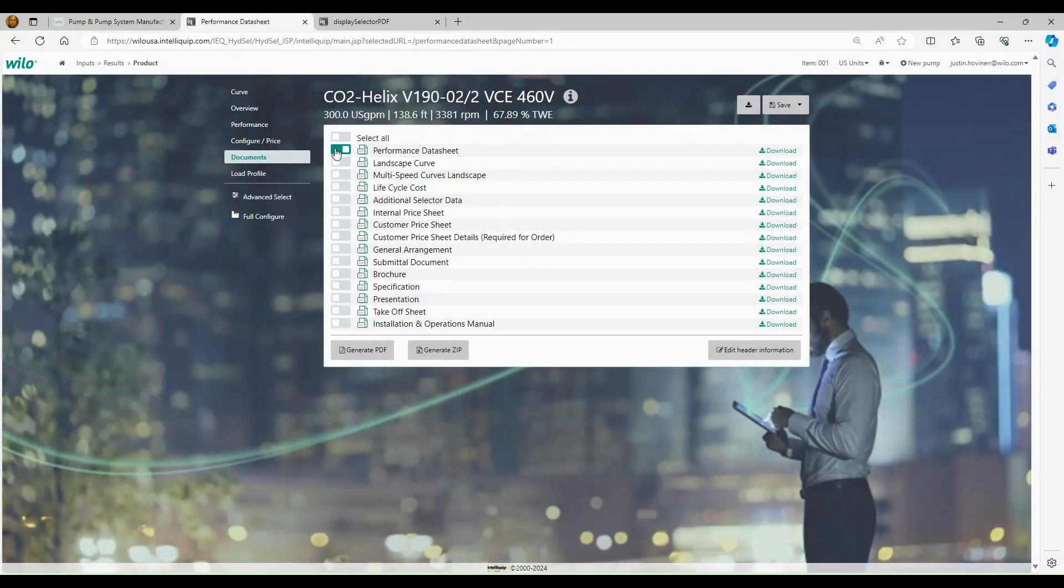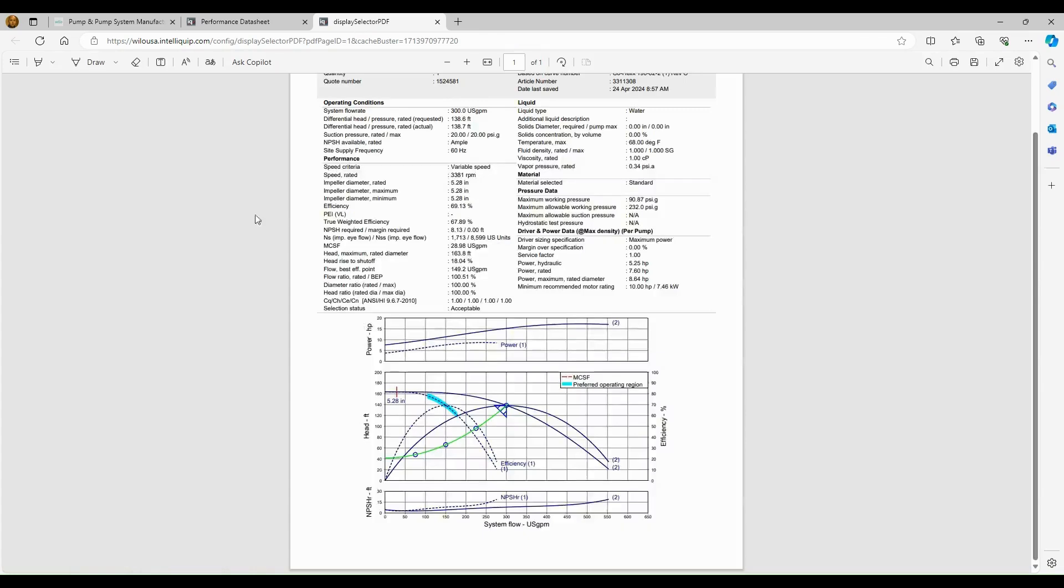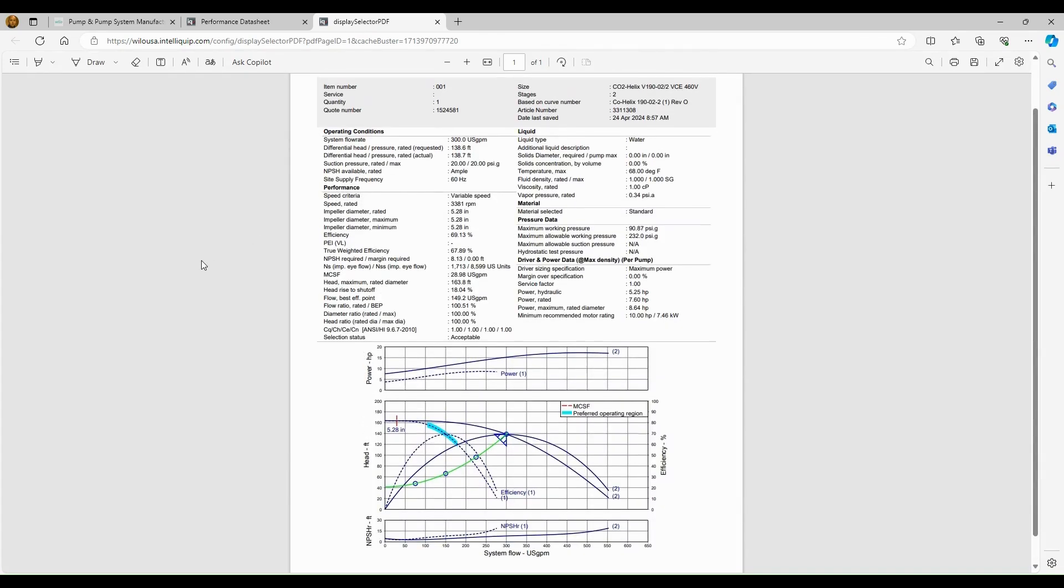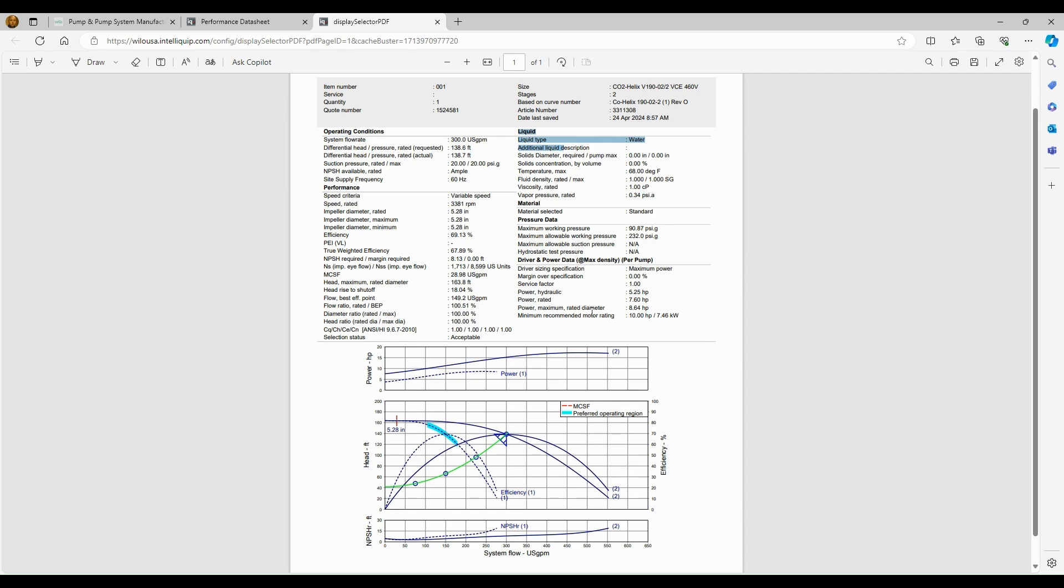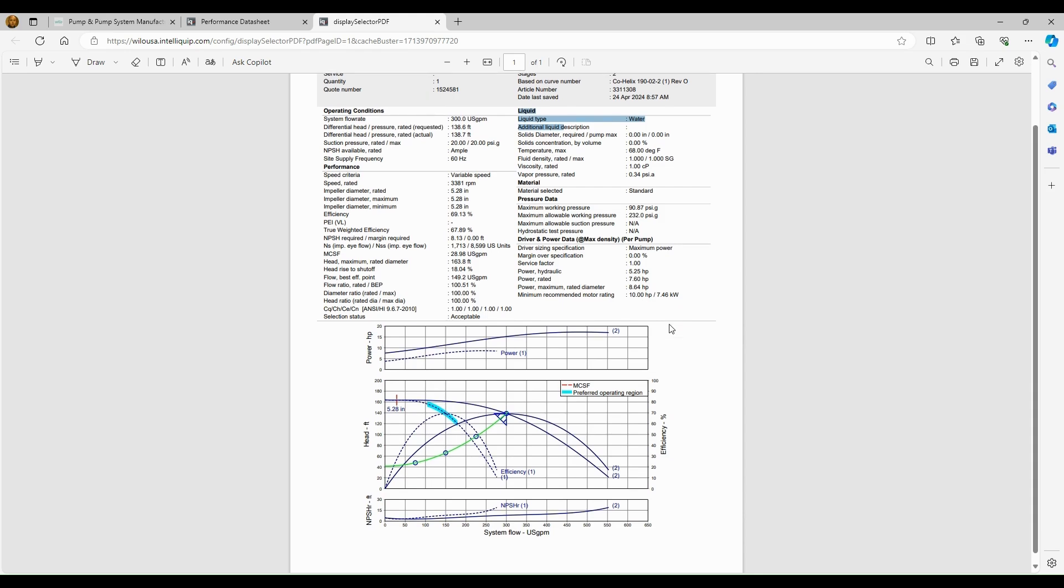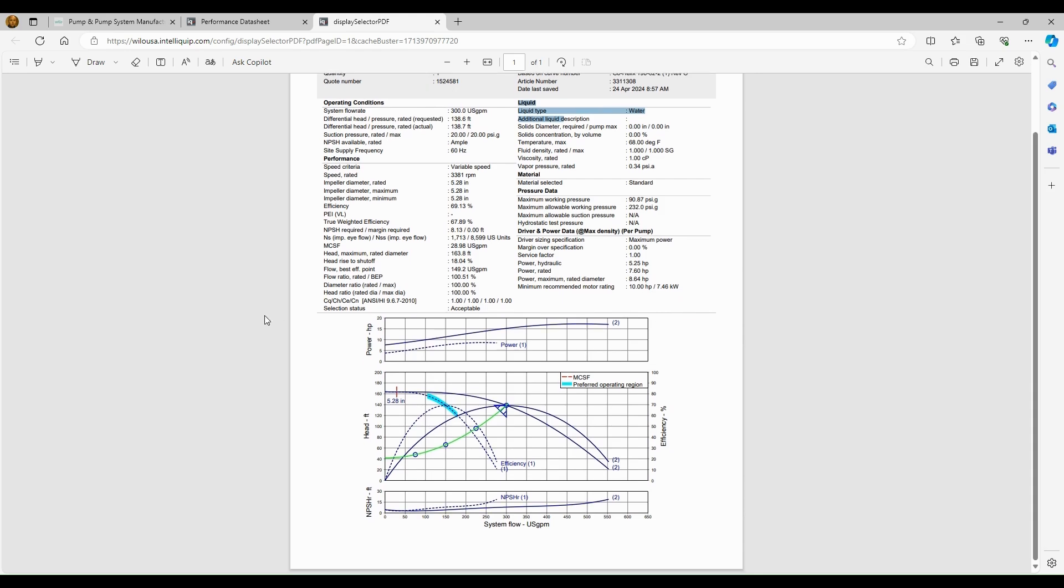Now we're going to review the rest of the documents. The first document up here at the top is going to be our performance data sheet. So we'll take a look at what's included in this. So we're going to have our operating conditions, our performance criteria at the rated speed of 3381 RPM. We need to hit this operating condition. We have our liquid at 68 degrees Fahrenheit, which can be changed in the selector. And that will change the density of the liquid if you do change it. So it could potentially affect motor size. And then we have our driver power and data over here, which will show us our rated horsepower, the max horsepower, and the overall motor size on this system. We also have horsepower shown below, our performance in flow and head, and then we do list our NPSH values.